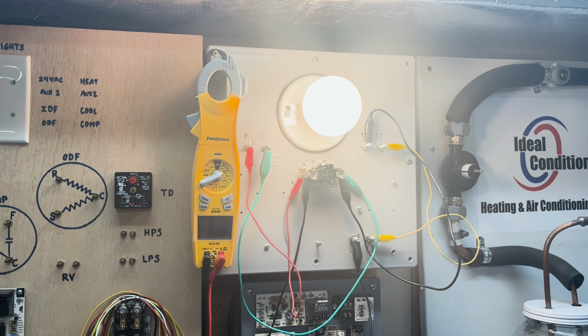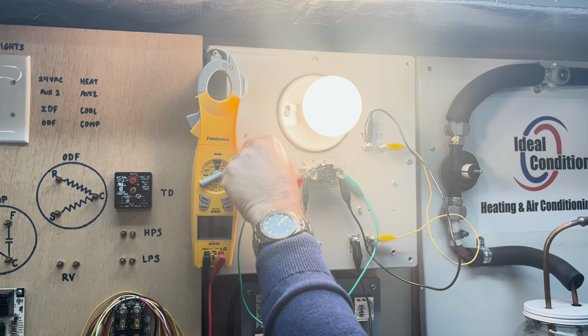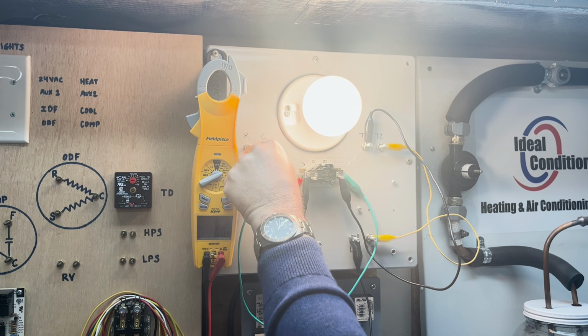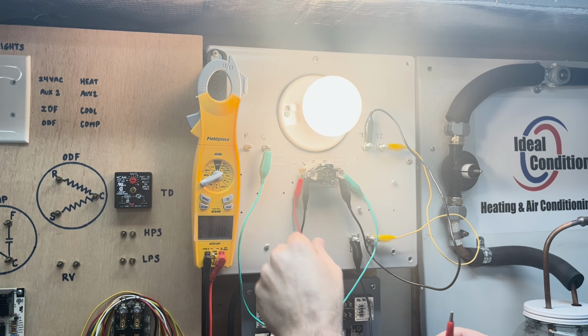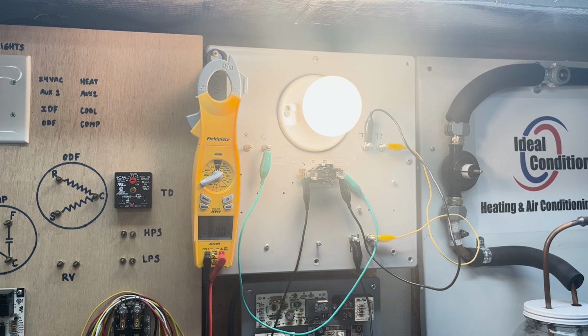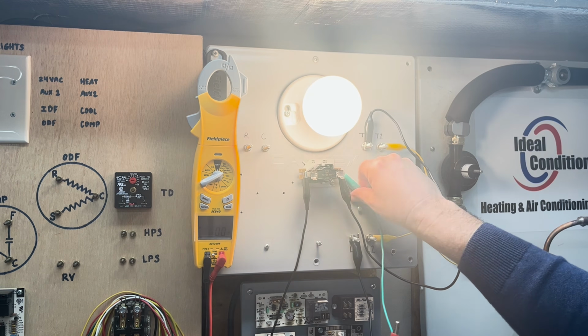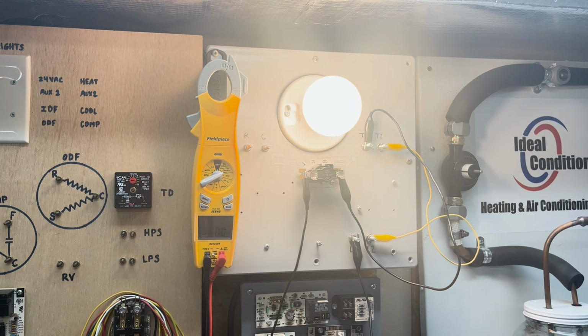Now, when we lose the G call, because we're going to be wiring it up for a fan motor, blower motor, it still runs. Matter of fact, let's go ahead and remove all these low voltage wires. It is still running. That thermal disc has to cool down. And so it's slowly cooling down, and once it cools down to a point, it'll break contact, and the load will lose 1 leg of power, and it can't run.